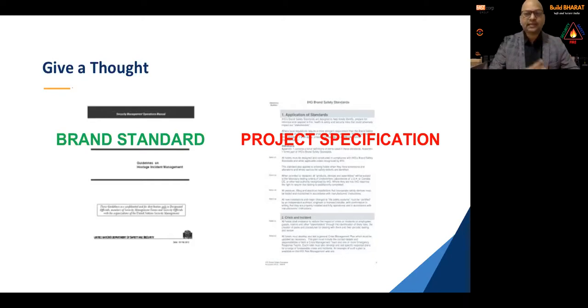And it should be end to end, not just SITC. SITC is a common term used in the industry: supply, installation, testing, commissioning. But in my experience, the last component, testing and commissioning, is very silent, because people see only supply and installation, certify the bill, and close the project. The fire alarm panel never gets commissioned or tested, pumps never get tested or commissioned, never get integrated with auxiliary systems, because we don't give justice to testing, commissioning, and the handover process.